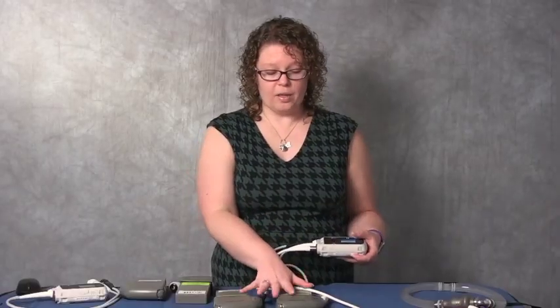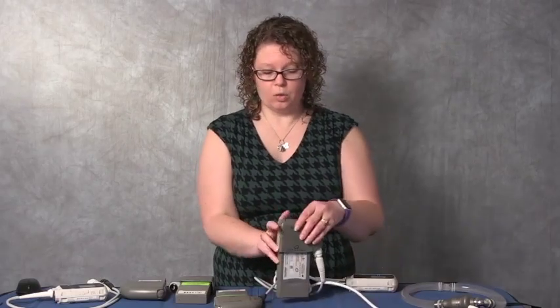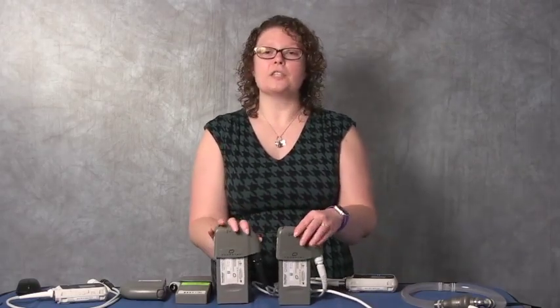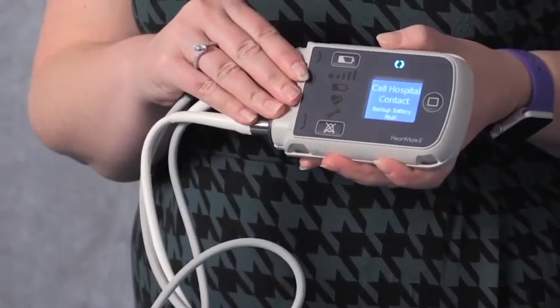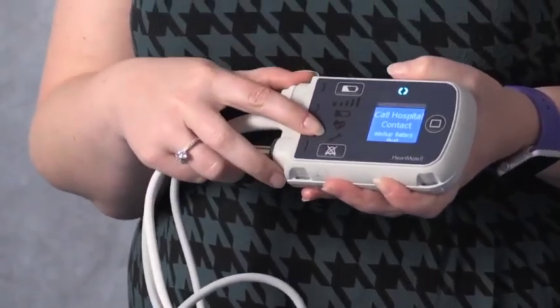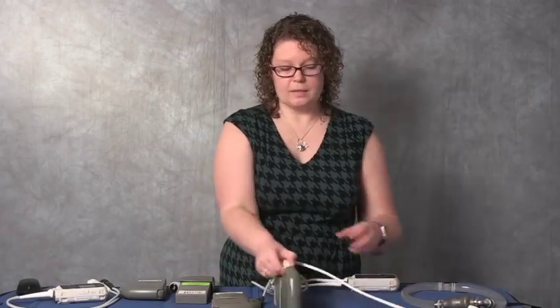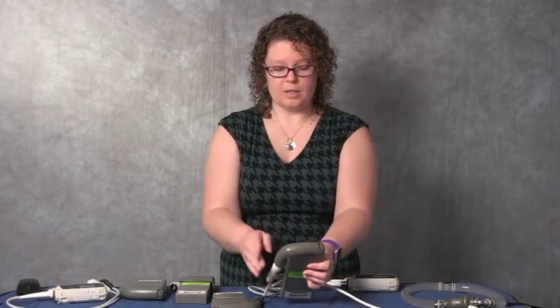Here I also have the batteries connected to the controller. A pair of batteries lasts for 10 to 12 hours. Another thing that I wanted to demonstrate today is how to change the HeartMate 2 controller. I have this controller specifically set to give us a yellow wrench alarm. And so I'll reset the silence so that you can hear what it sounds like.